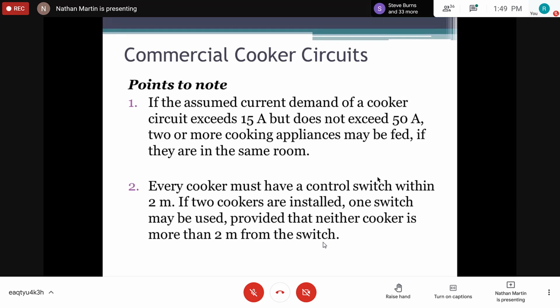Every cooker must have a control switch within 2 meters, right? So we're talking about 6 feet. So within 6 feet of the cooker, you must have a switch that can switch it off. This is stated by regulation because of the heat, right, and for safety reasons. So you must have a quick means of isolating or turning the power off from reaching the cooking unit.